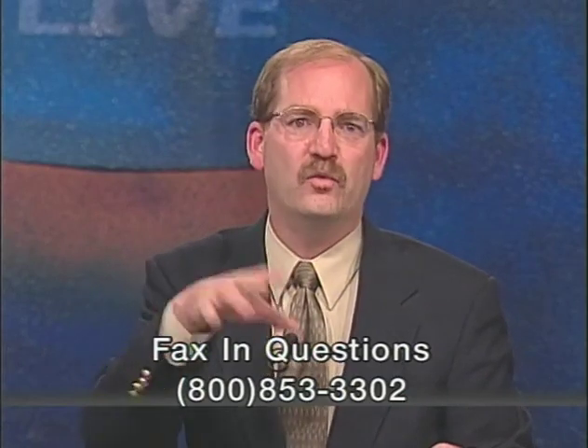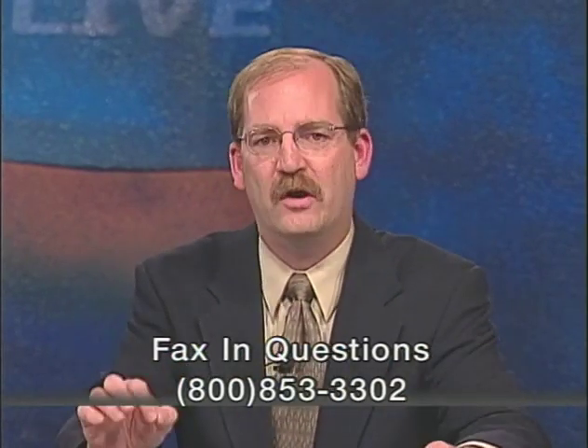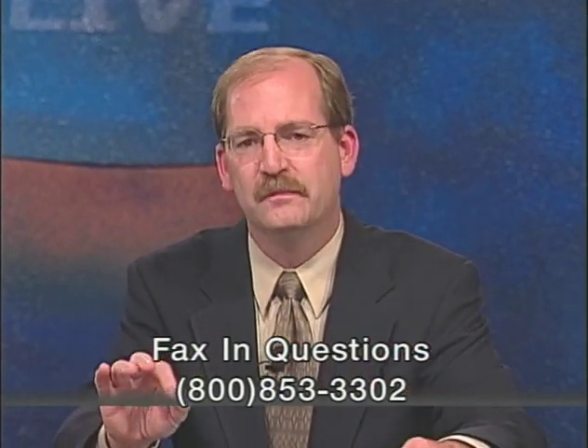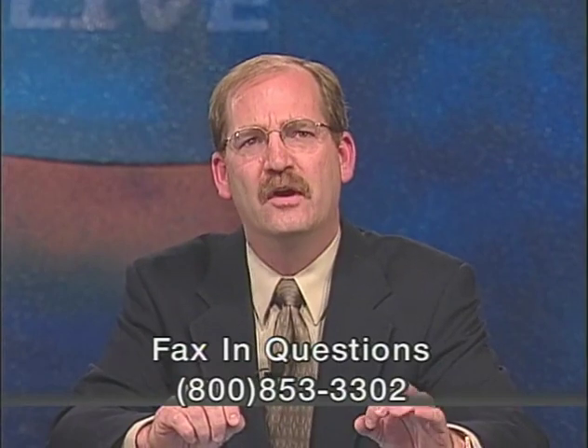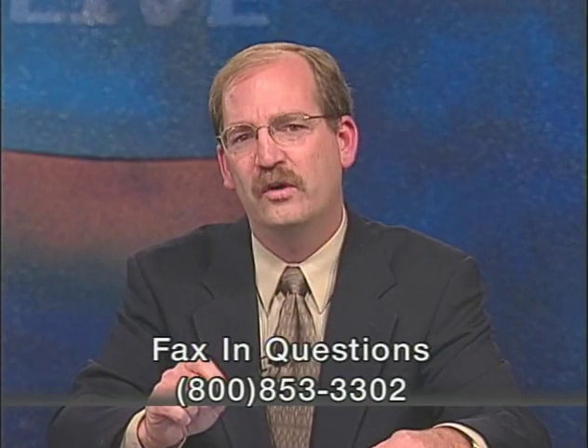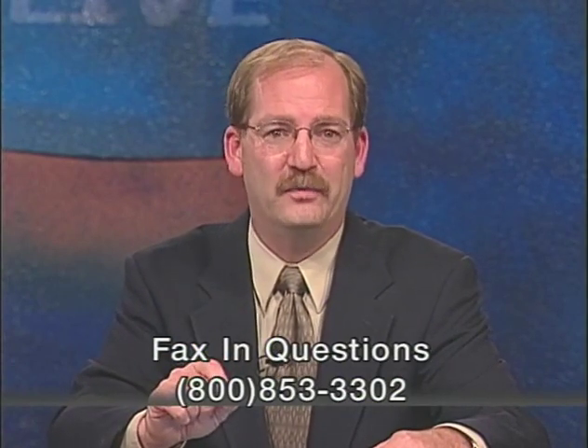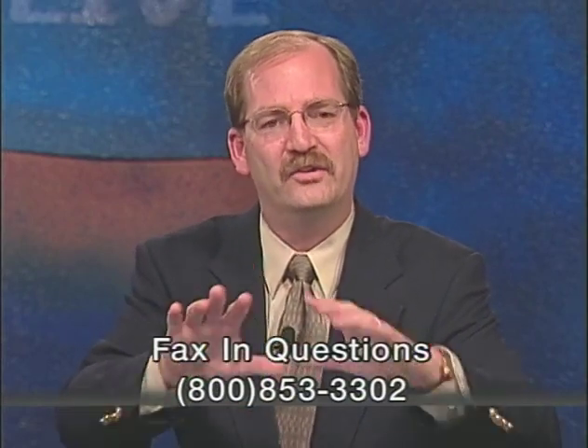Now, one real important point to make here is that we need to make sure that we don't just look at the HVAC side and say we take it out of the room and we'll be within the new sound level requirements. You need to analyze it. This was one example. Secondly, one thing Dave said there was that we need to look at the other sound sources. There have actually been studies done which showed that the lighting alone caused background sounds of 35 dBA. So we need to once again look at it from a holistic approach. Dave, let's take it down the home stretch and talk a little bit about the central systems.